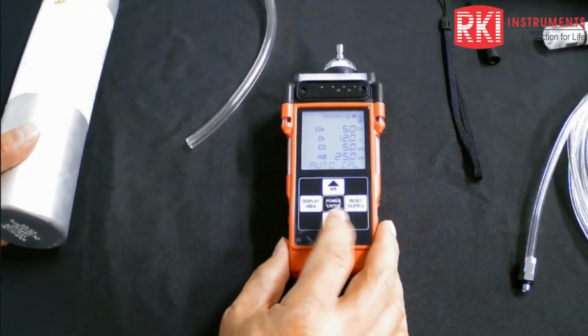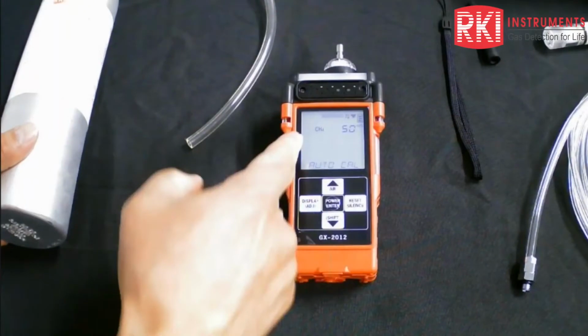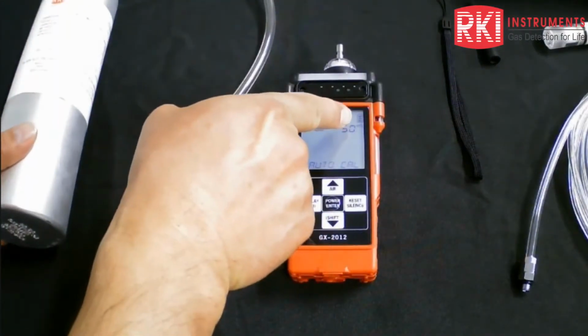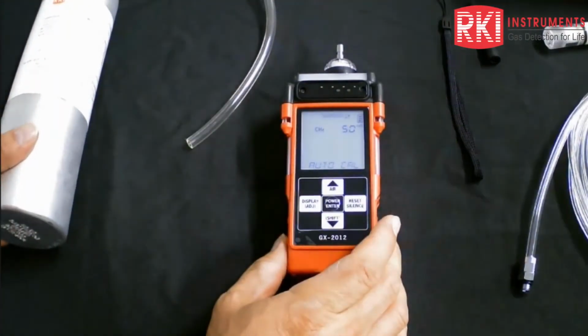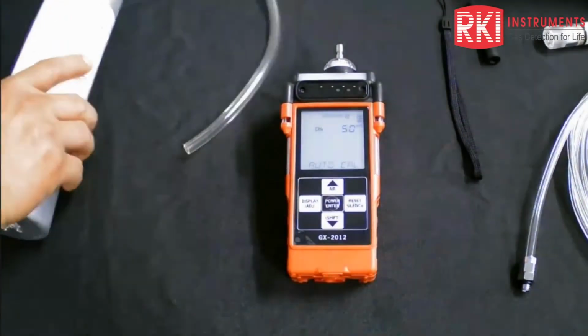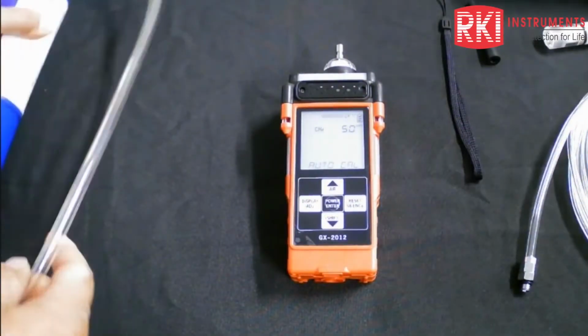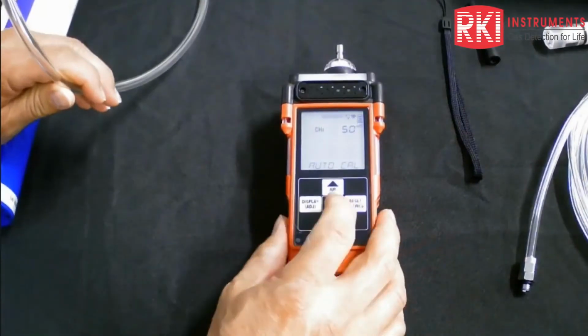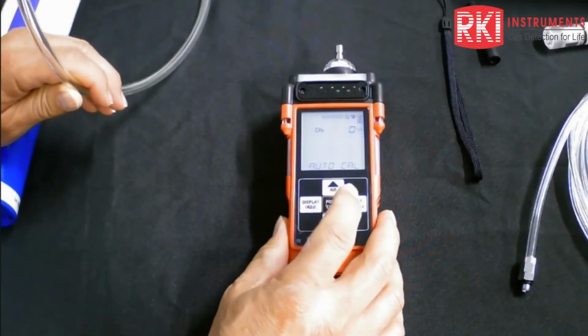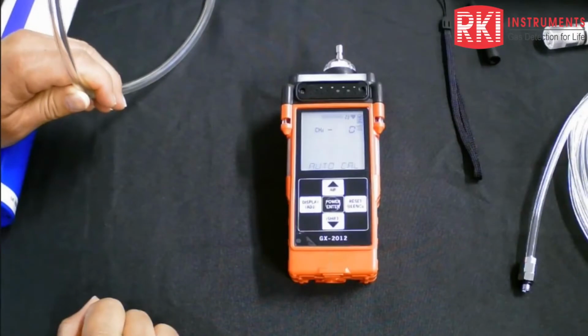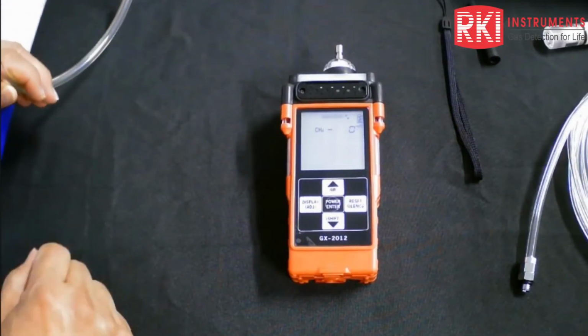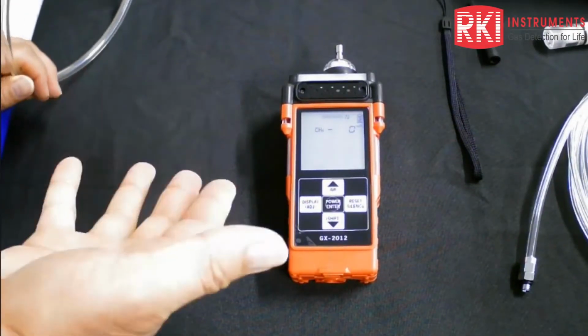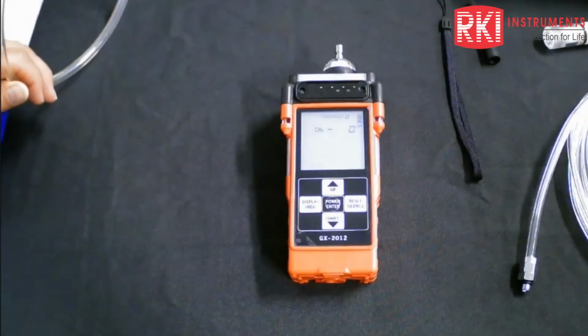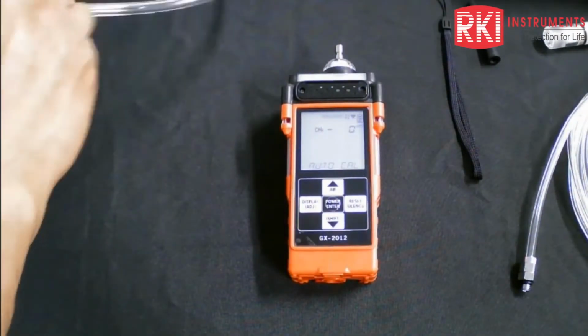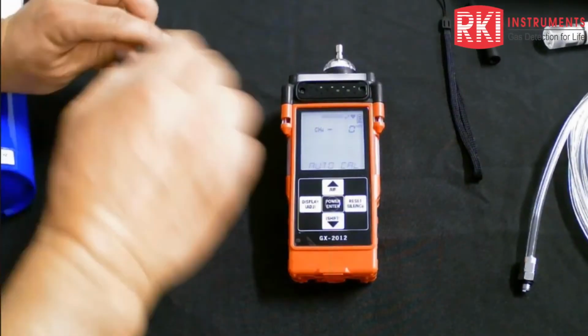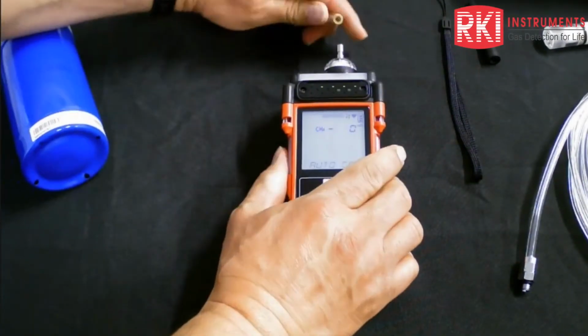Okay, and this time I'm going to press the down button, and that brings up my percent by volume. It does say vol percent next to that 50, methane 50 there. Okay, then I will get my other cylinder ready here, and I'll press the enter button again, because 50% by volume is what my cylinder says. It's got 50% by volume. You may have 100% by volume. We also sell those cylinder gases. And so that auto cal value might be set to either 50 or 100.